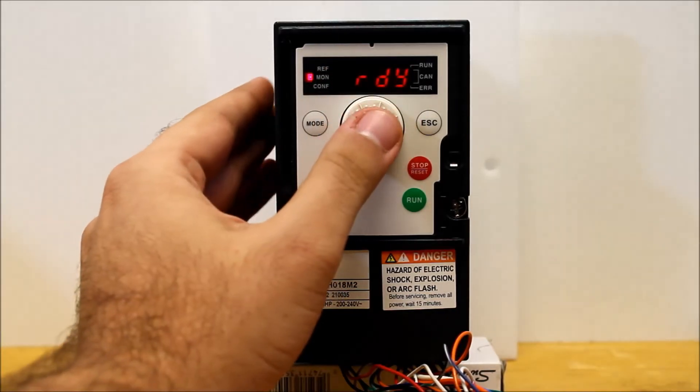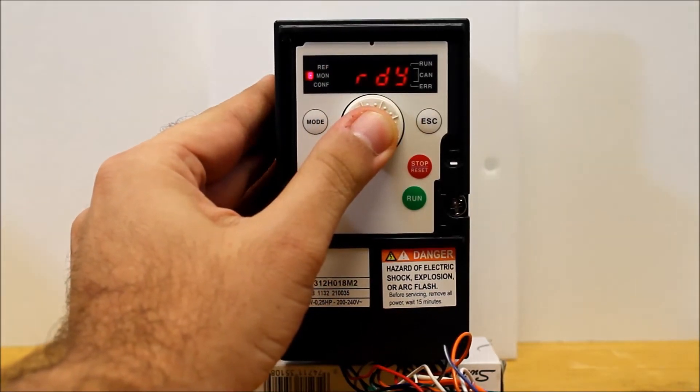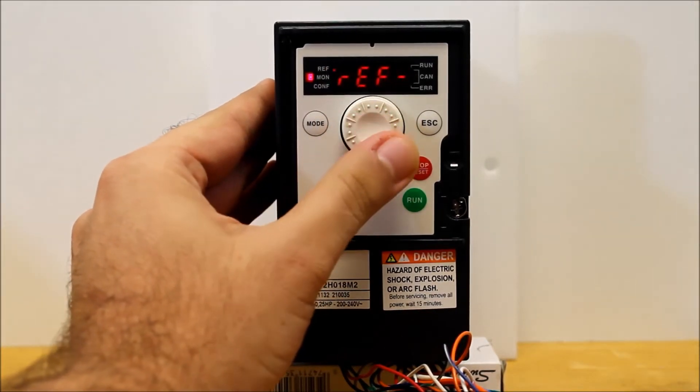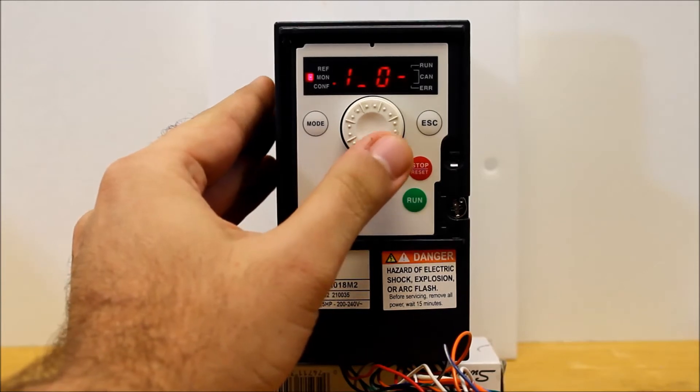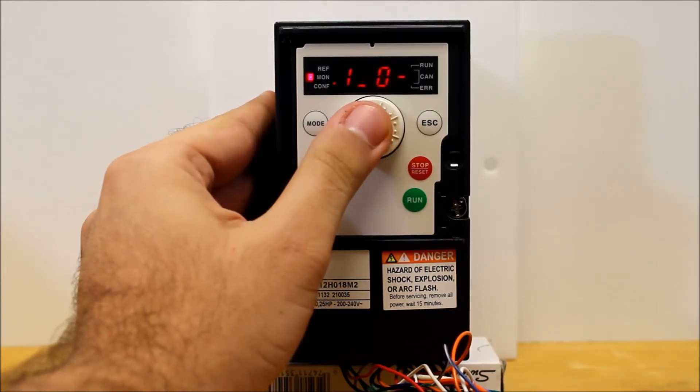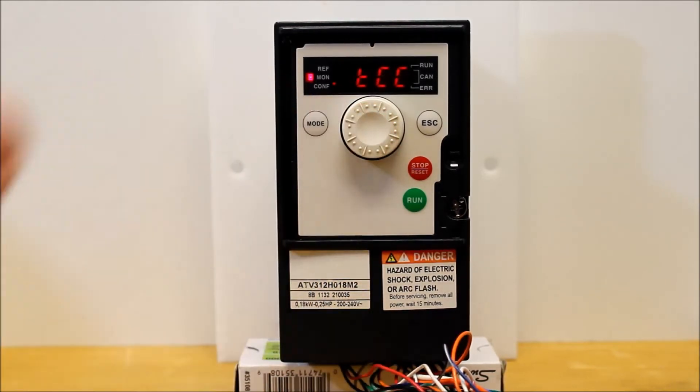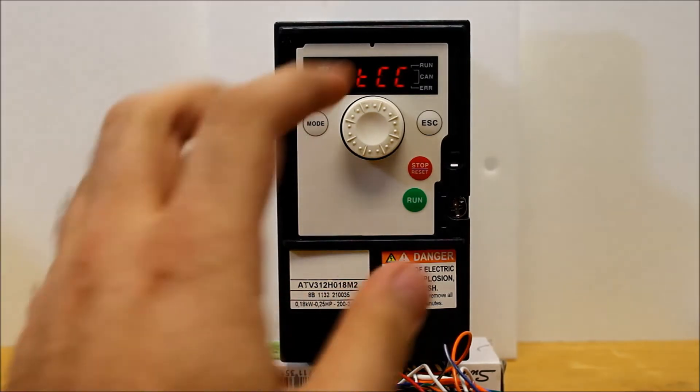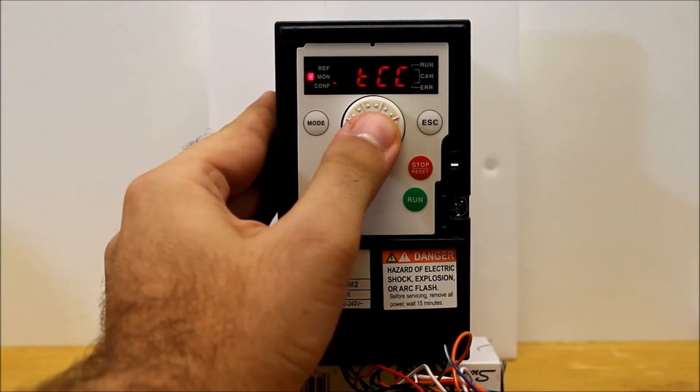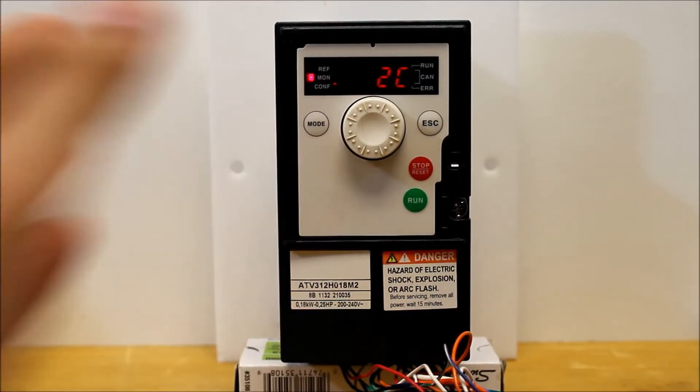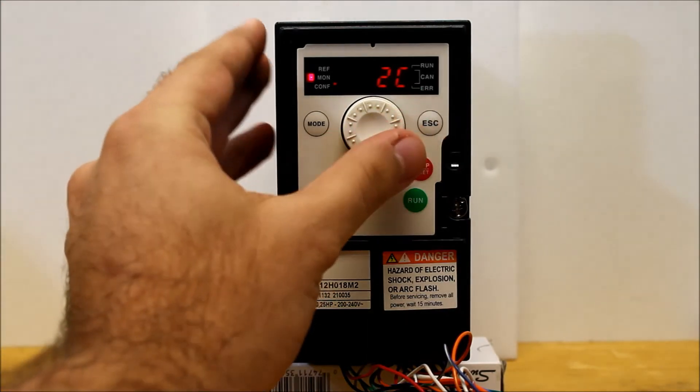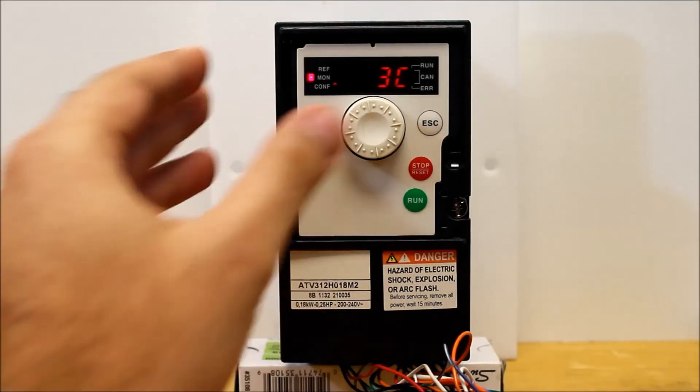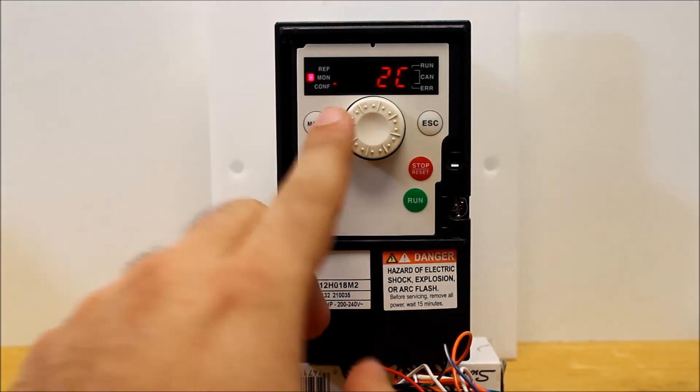So we can enter from your main display, scroll down to I-O, inputs and outputs menu. The first parameter is TCC, and when you enter on that, you want that to be on 2C for two-wire. You have the option of making it 3C as well, but make sure it's on 2C.